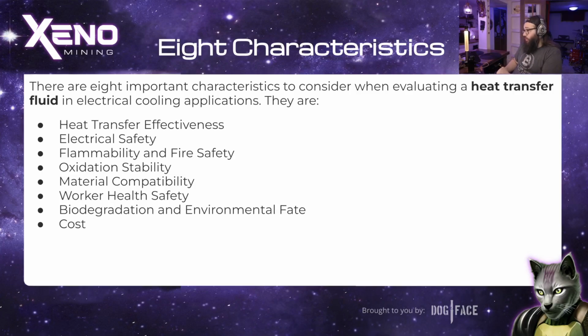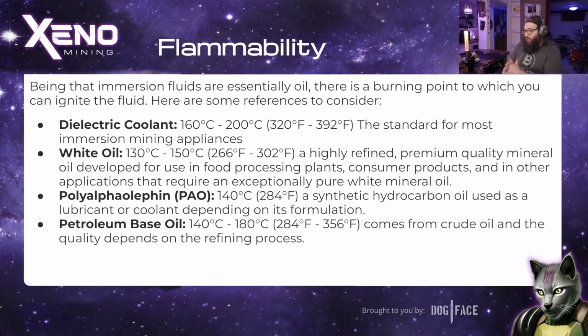So let's take a look. Flammability: being that immersion fluids are essentially oil, there is a burning point. Here are some of those points I've been able to look up. Dielectric coolant is roughly somewhere between 160 to 200 degrees Celsius, or 320 to 392 degrees Fahrenheit, which is the standard for most immersion mining appliances.